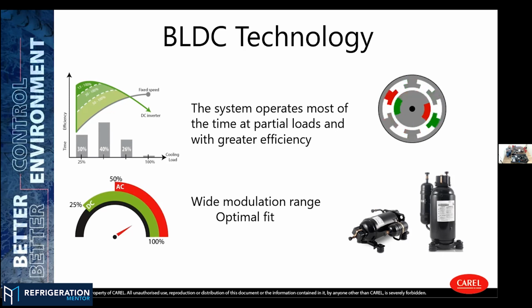The BLDC technology is a type of compressor that was designed to be variable. So we don't have restrictions directly related to the speed of the compressor and the lubrication part. I will show you later how it goes. And since we have this condition, we can have the compressor modulating in a very wide range. Here in the graph, just as a comparison, I can show you how the performance of an on-off motor, a fixed speed motor, and a variable speed motor goes under different cooling loads.